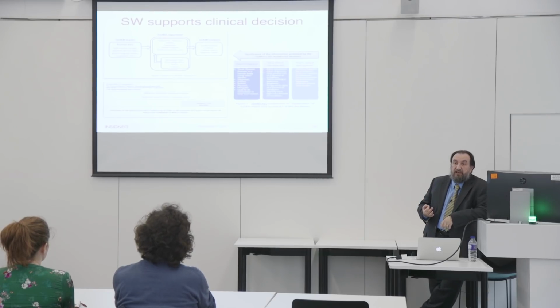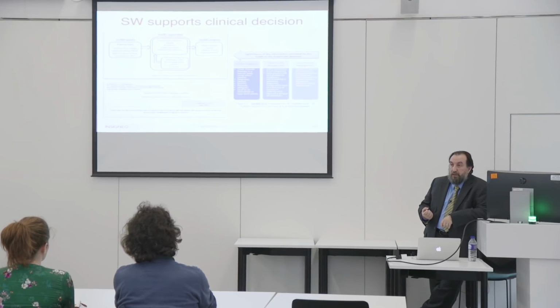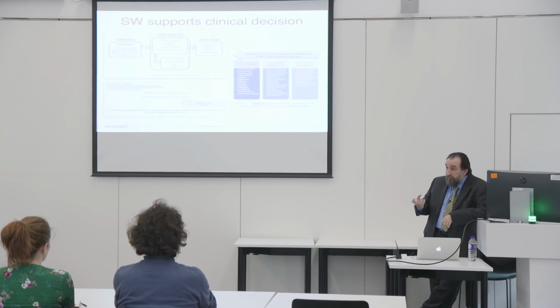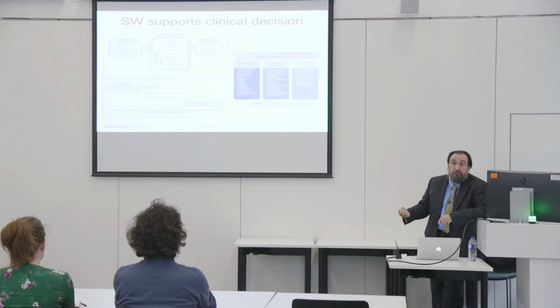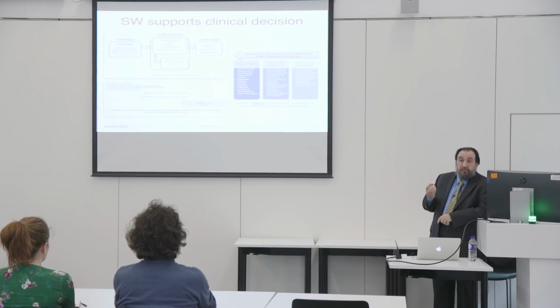The two key elements that I want to stress here are these. The first is a recognition that in software as a medical device there are three moving parts. The inputs, the information provided to the software, which might come from data you measure on the patient separately, or from sensors that continuously feed the software, for example in a pacemaker. So inputs are one source of risk that needs to be tested clinically. There are outputs, what the software predicts and provides. There are risks there. And then there is the algorithmic part within the software.